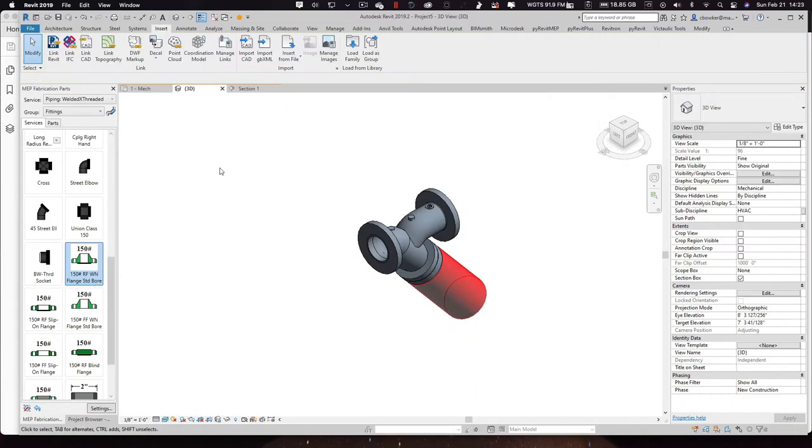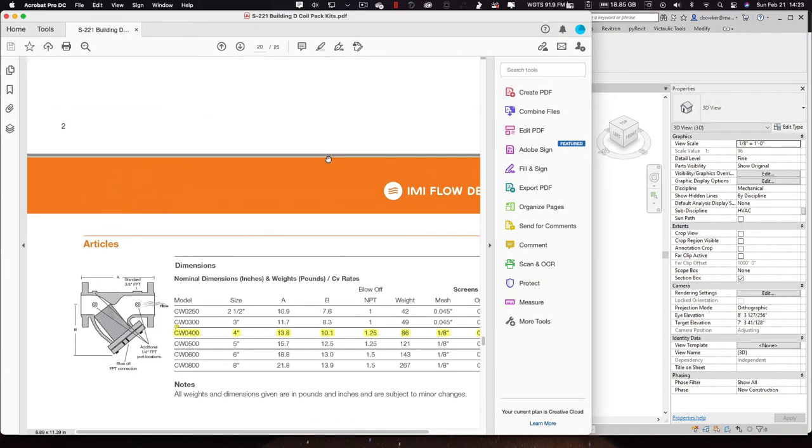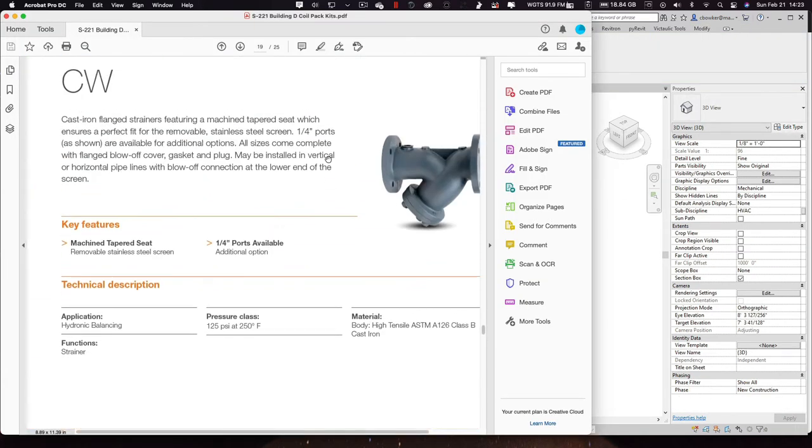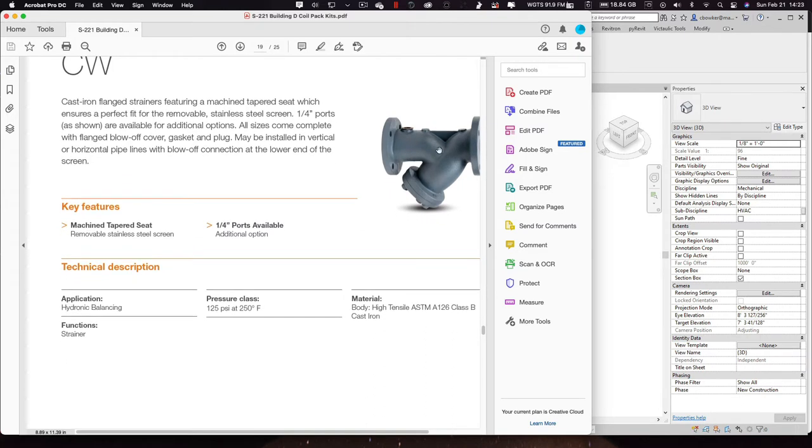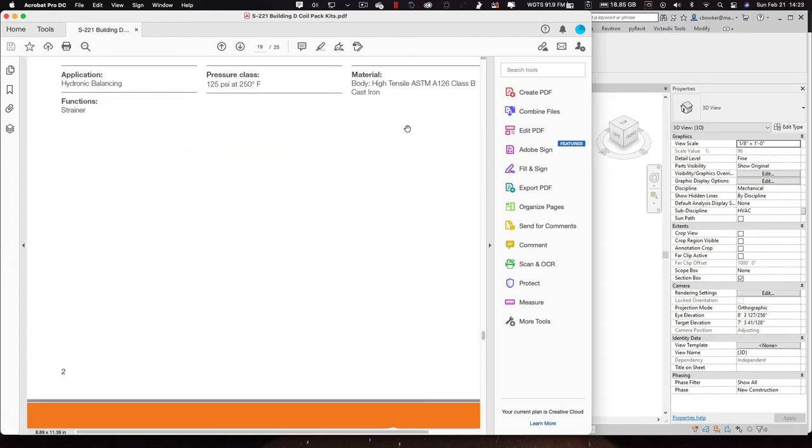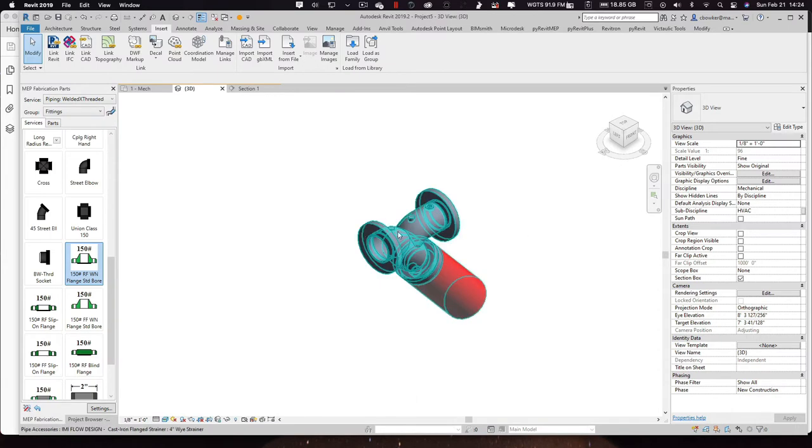But also in the submittal, when you look at the actual picture of the device itself, it shows two test ports and a three-quarter inch blow-off. In the submittal here, it only shows one test port and a three-quarter inch blow-off. So I elected to make it look like what the actual product looks like. So I put these ports in.